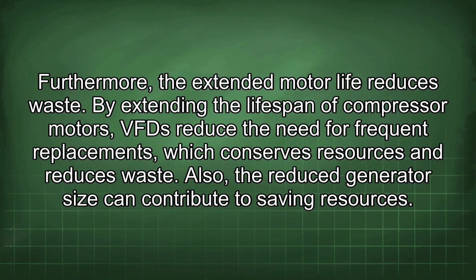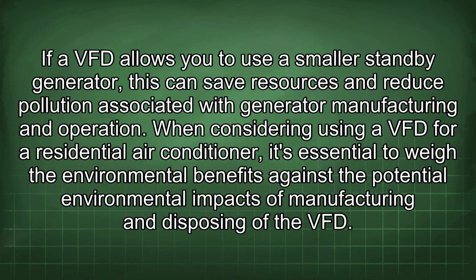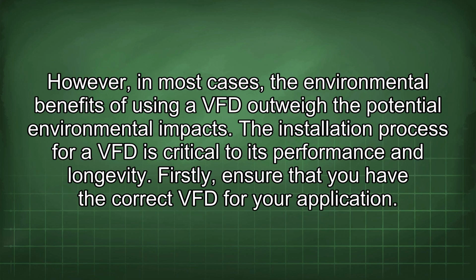Furthermore, the extended motor life reduces waste. By extending the lifespan of compressor motors, VFDs reduce the need for frequent replacements, which conserves resources and reduces waste. Also, the reduced generator size can contribute to saving resources. If a VFD allows you to use a smaller standby generator, this can save resources and reduce pollution associated with generator manufacturing and operation. When considering using a VFD for a residential air conditioner, it's essential to weigh the environmental benefits against the potential environmental impacts of manufacturing and disposing of the VFD. However, in most cases, the environmental benefits of using a VFD outweigh the potential environmental impacts.